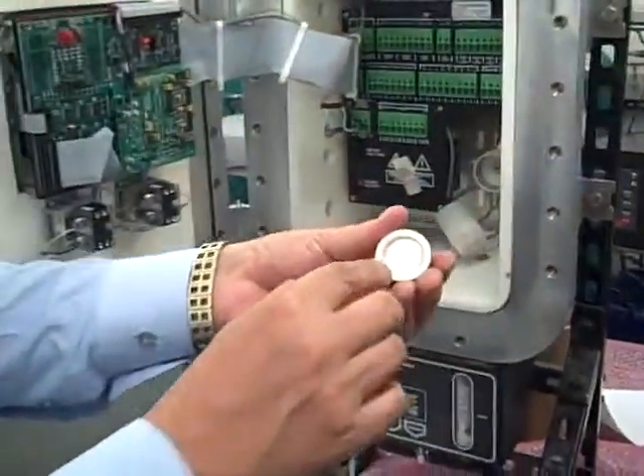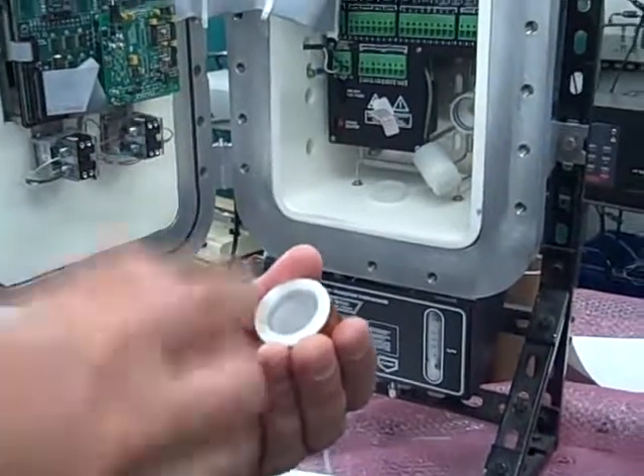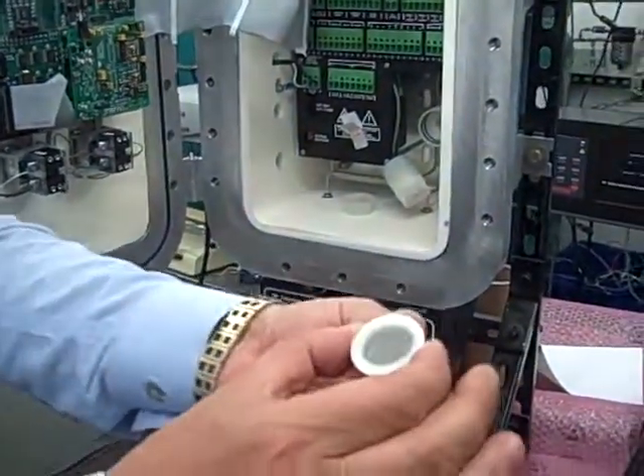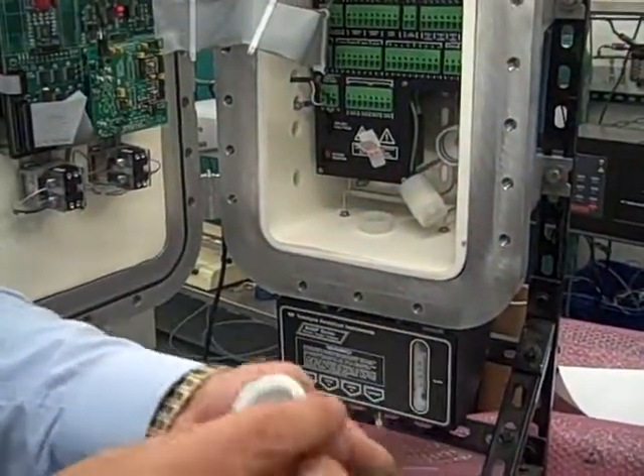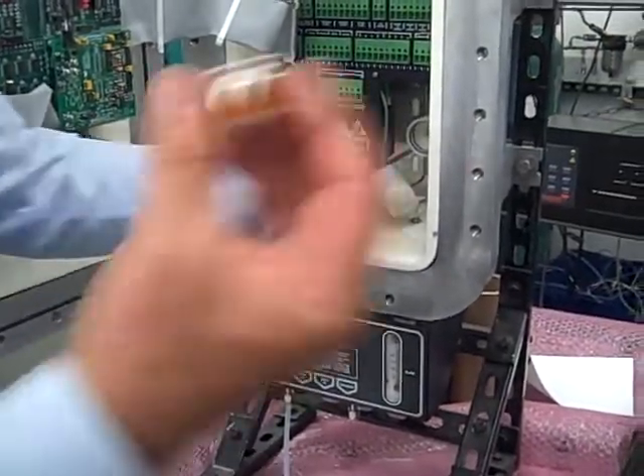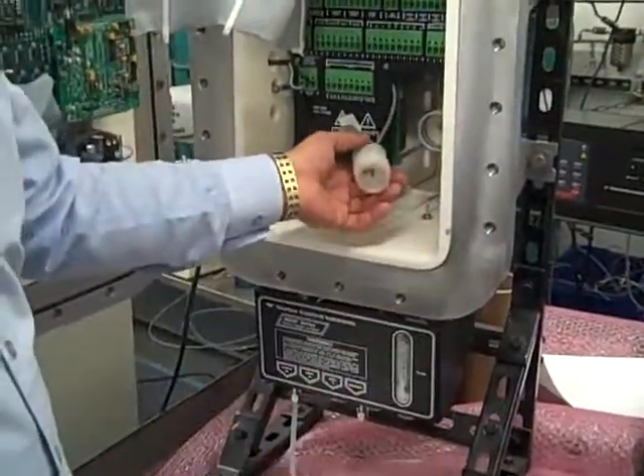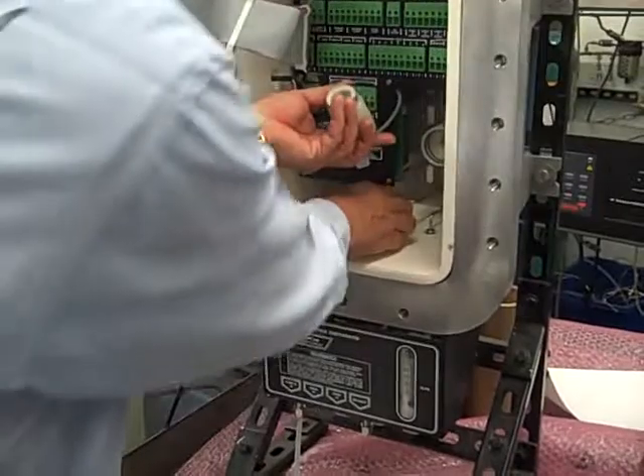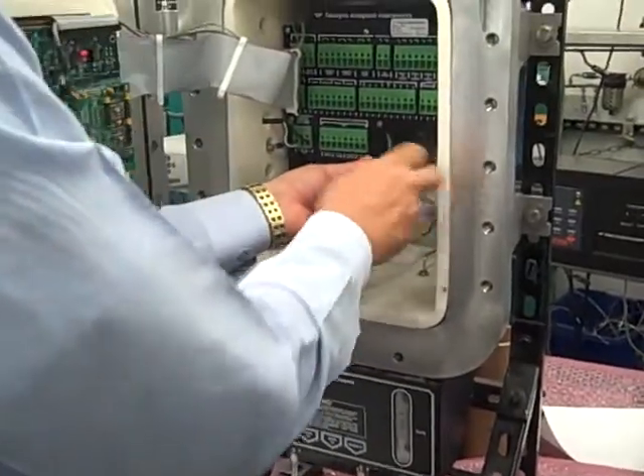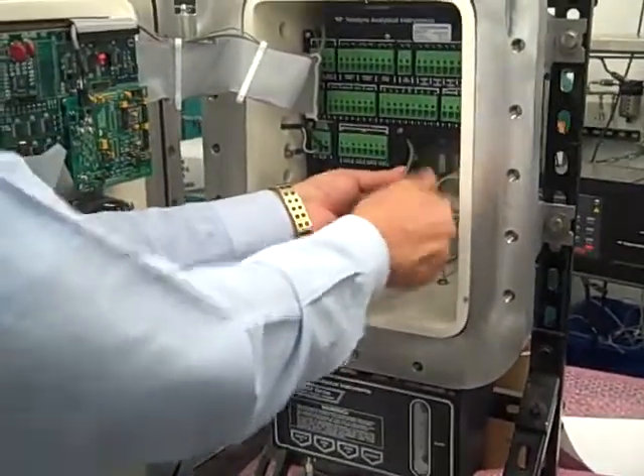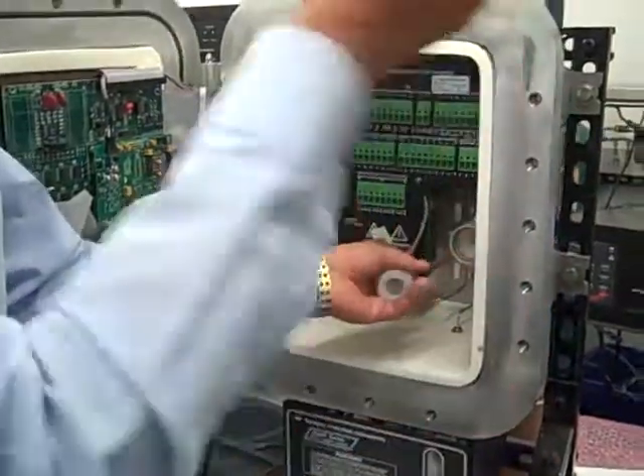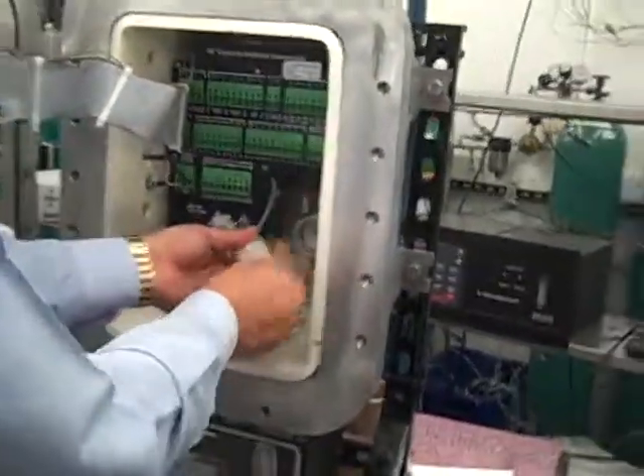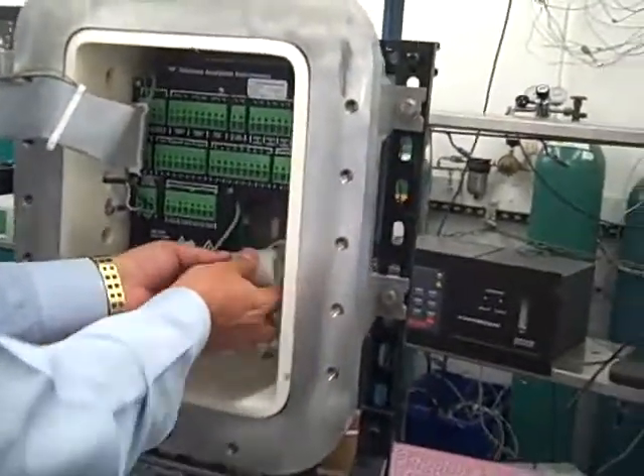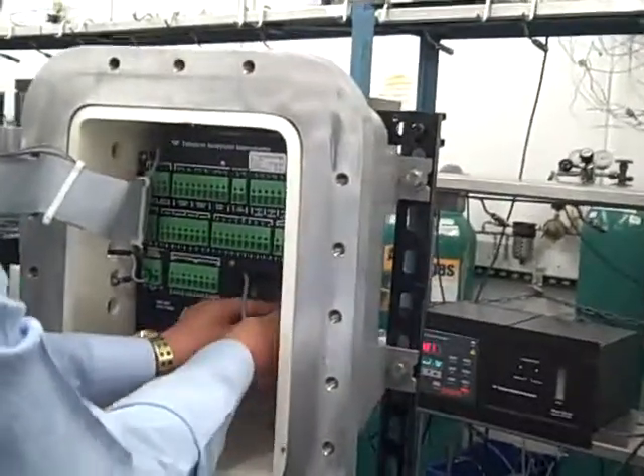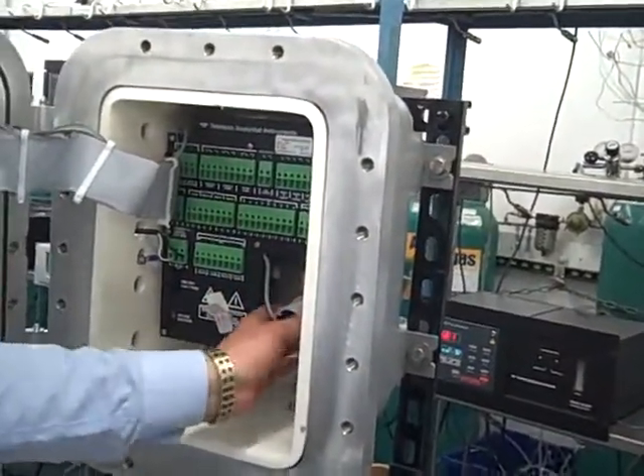And this is the sensing surface. This is where the oxygen comes in and reacts with the sensor's chemicals and structure to provide the output signal. So get this sensor out of the bag quickly, put it in there, screw the cap in. If it's that type of unit, if it's a 3020T, there'll be a latching mechanism that you put it in. In any event, put the sensor in. It's very simple, and this type of sensor will last anywhere from 6 months to 1 year in service.